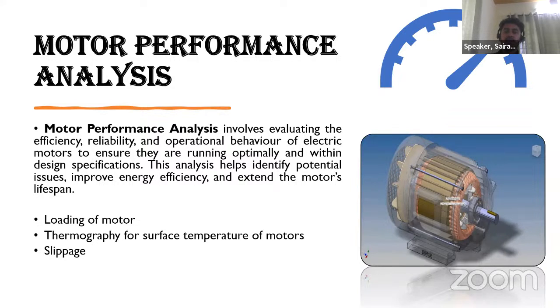From an energy assessment point of view, motor performance analysis is done in 3 ways. Like I said for the transformer, the losses in this motor can't be found at the site. That is not practically possible, but it is possible at the laboratories. Even in engineering, in some of the laboratories, you could have performed experiments on finding the performance of motors also. So here we will be checking for the loading of motors. Then we will be checking for the surface temperature of motors with thermography.